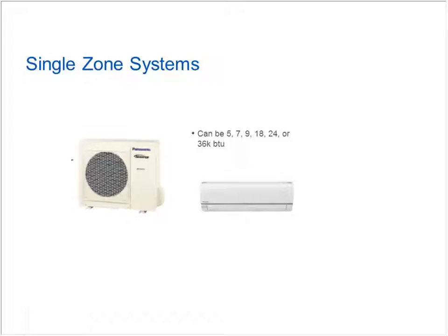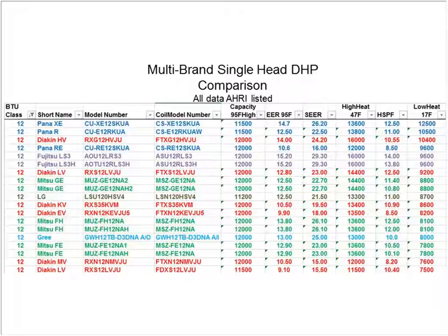There are single zone systems, and they can be 5, 7, 9, 18,000, 24,000, 36,000 BTU. If you really want to throw money at it, you can go to the VRF stuff, which is even higher, but there's not much in VRF in single zone. What we look at, and I go back to the AHRI listing, when I talk to builders, our concern is never how it performs at 47 degrees. Every heat pump that you look at will be better than electric heat at 47 degrees, no matter what. I mean, they're all good.